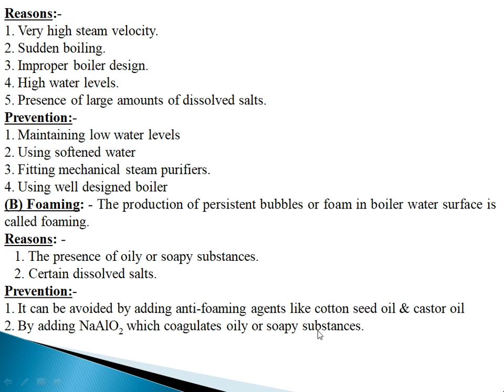What is meant by foaming? Foaming is nothing but the production of persistent bubbles or foam on the boiler water surface. If the water in boilers contains oil or soapy substances, or certain dissolved salts, it causes foaming. Foaming can be prevented by adding anti-foaming agents like cottonseed oil and castor oil. Oil or soapy substances in the boiler water can be removed by adding sodium aluminate, which coagulates the oil or soapy substances.